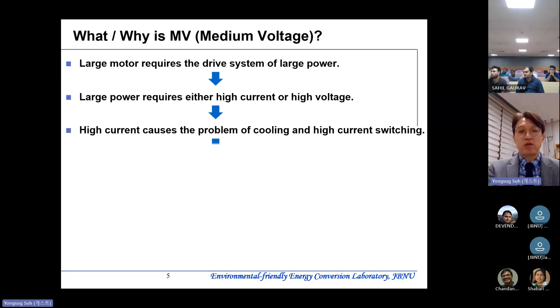Dealing with high current is a very challenging issue, so naturally engineers pay attention to high voltage instead of high current. High voltage also has insulation problems, but compared to cooling, insulation coordination technology is more mature. So in general, engineers of medium voltage drive systems push high voltage instead of high current.